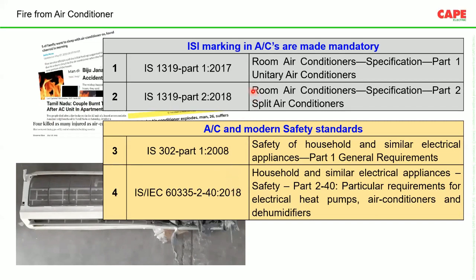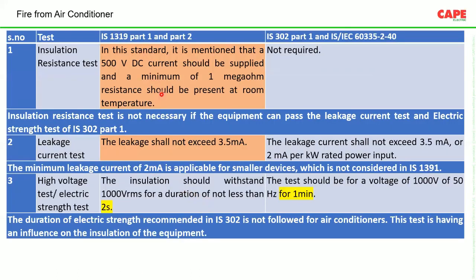The issue is mandatory marking. The recommended standard is only 1319, but in the letter, mandatory marking for 302 and 60335 2-40 is not mentioned. As a result, there is a chance that the manufacturer may not test as per 302 or 60335 2-40. So when you buy an air conditioner, you must check whether it is ISI marked. Plus, please also check whether the air conditioner is tested for all the safety parameters as per IS 302 and 60335. For example, I just made a comparison.